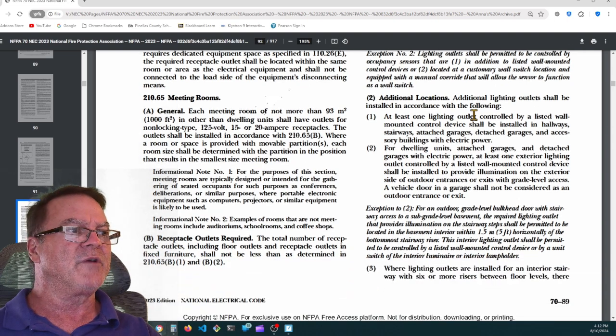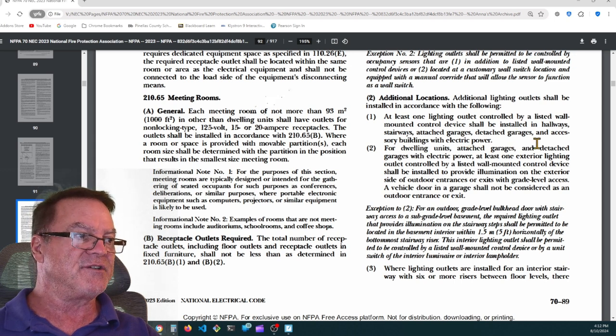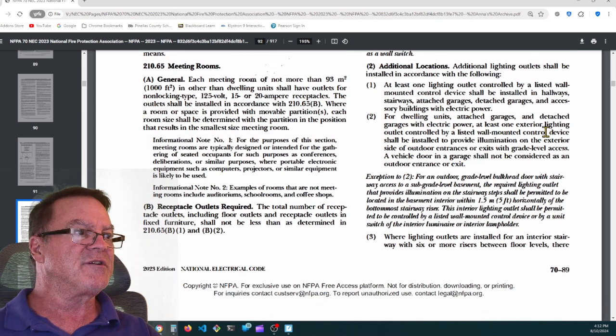And then 2 additional locations, additional lighting outlets shall be installed in accordance with the following. At least one lighting outlet controlled by a listed wall-mounted control device shall be installed in hallways, stairways, attached garages, detached garages, and accessory buildings with electric power. For dwelling units, attached garages, and detached garages with electric power, at least one exterior lighting outlet controlled by a listed wall-mounted control device shall be installed to provide illumination on the exterior side of outdoor entrances or exits with grade level access. A vehicle door in a garage shall not be considered as an outdoor entrance or exit.